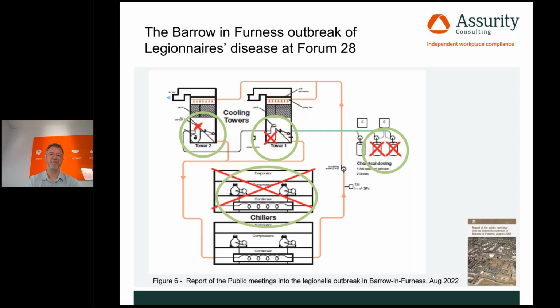As a result of particularly those two things, one of the chillers had fallen over under the demands placed upon it, and they were running off one chiller. This was causing - you'll see if you look just over the top of the two cooling tower pictures - where ductwork had been manufactured to take the extract air out, which effectively came out the side of the building and into this alleyway.